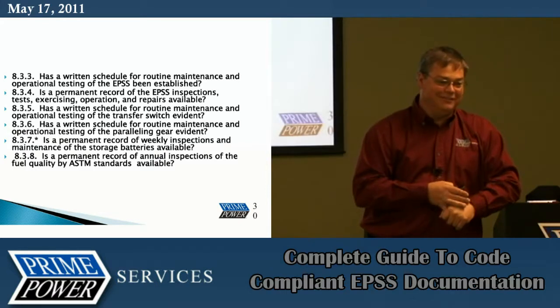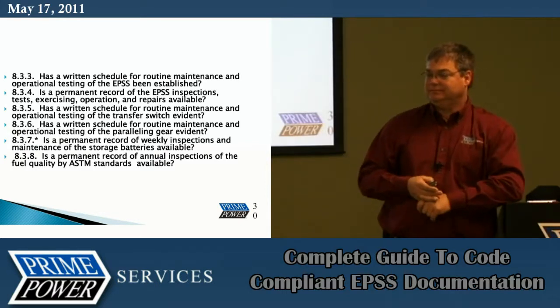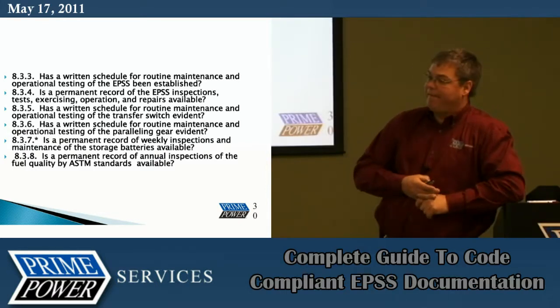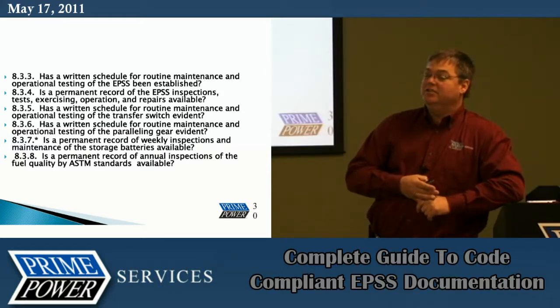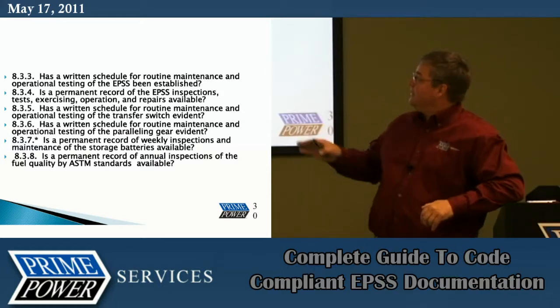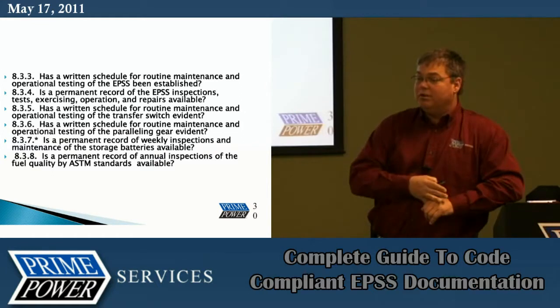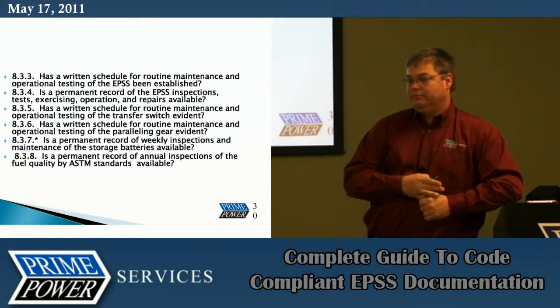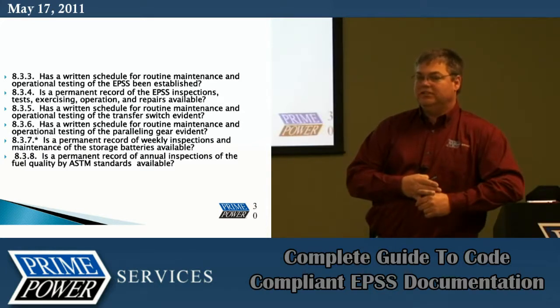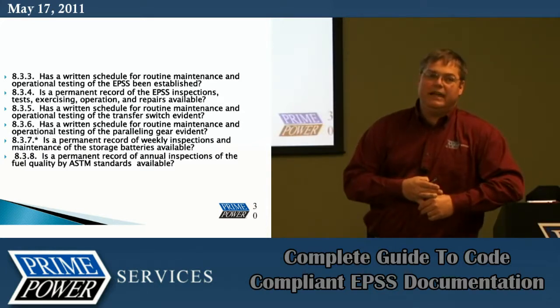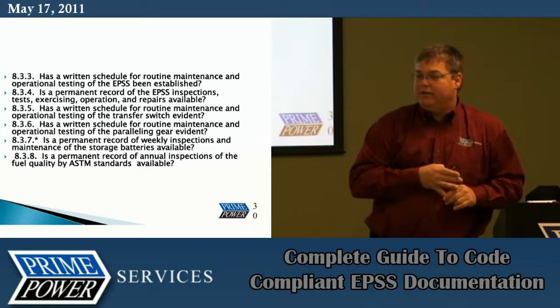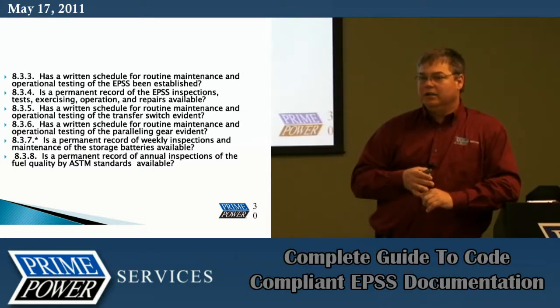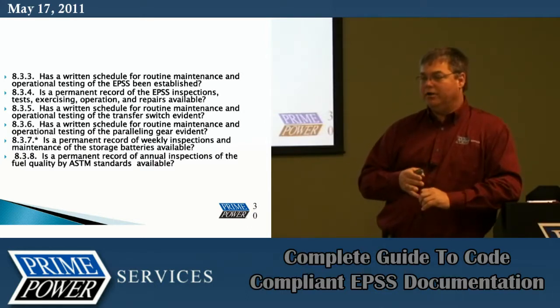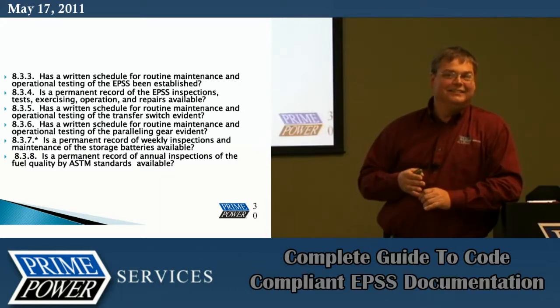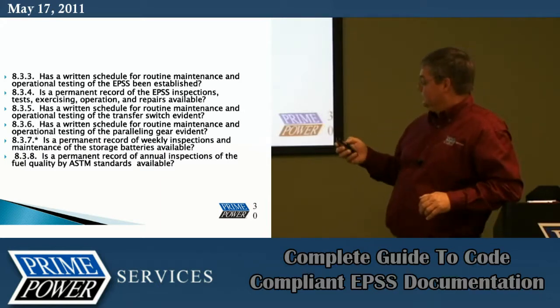You're toast. So on 8.3.4, you keep records back 7 years? Generally speaking, that's the term you'll find code-wise for 'permanent' records. But on the generator, I would keep it for the life of the unit. Anything directly related to life safety egress, I would keep for the life of the unit, because you never know when some idiot will come up with a lawyer 10 years from now claiming something wasn't maintained.